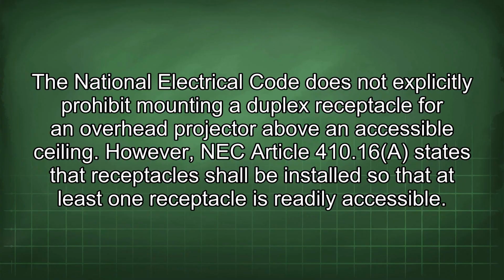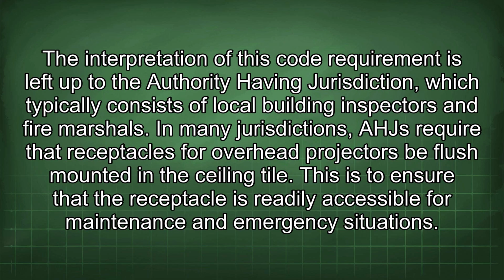The National Electrical Code does not explicitly prohibit mounting a duplex receptacle for an overhead projector above an accessible ceiling. However, NEC Article 410.16 states that receptacles shall be installed so that at least one receptacle is readily accessible. The interpretation of this code requirement is left up to the authority having jurisdiction, which typically consists of local building inspectors and fire marshals. In many jurisdictions, AHJs require that receptacles for overhead projectors be flush-mounted in the ceiling tile. This is to ensure that the receptacle is readily accessible for maintenance and emergency situations.